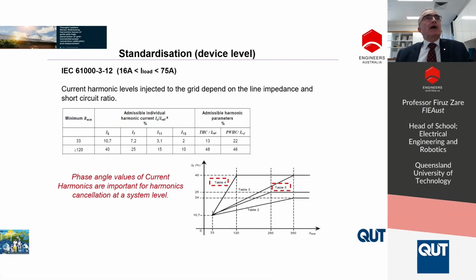Having said that, we have different standards, and I'm just trying to highlight one of them, IEC 61000-3-12, which is for three-phase, high power equipment, and we have different relaxations to decrease or control the harmonics in the network because of cancellation. Therefore, you see that under different conditions, based on the grid impedance, the type of transformer and the short circuit ratio, the device can generate different harmonics in the network.